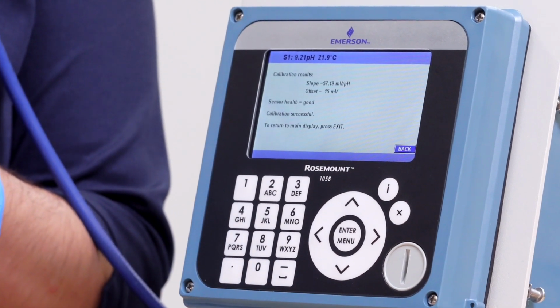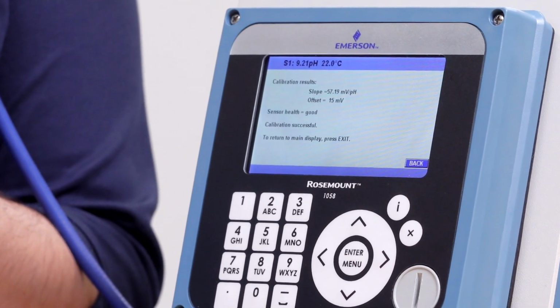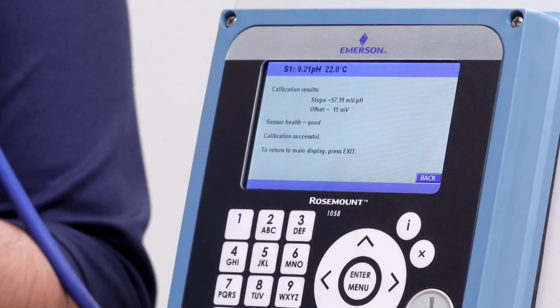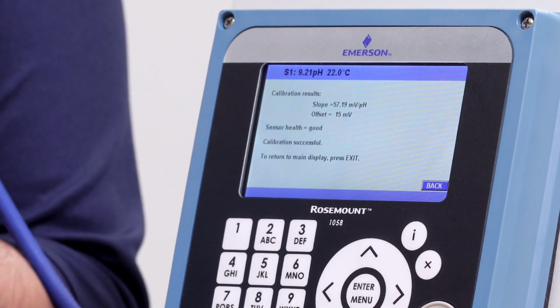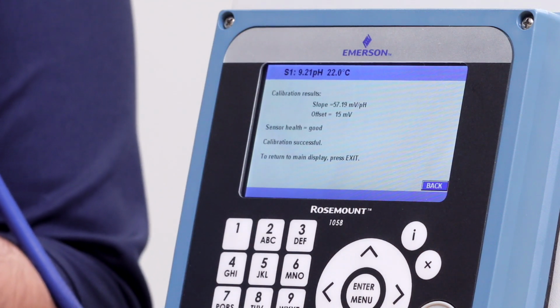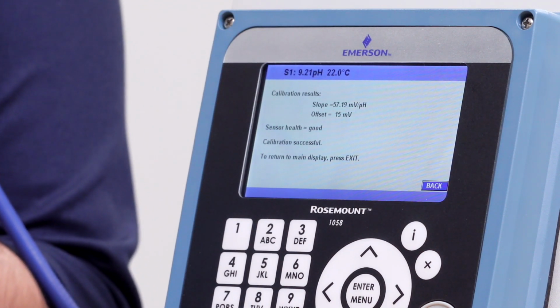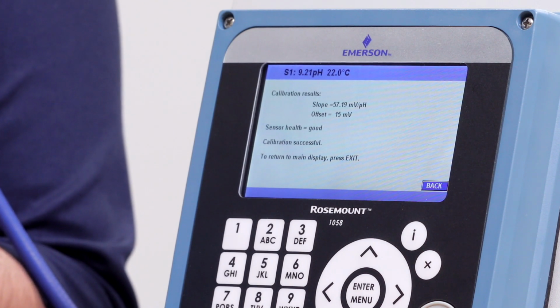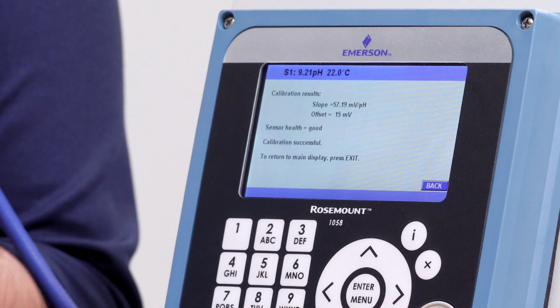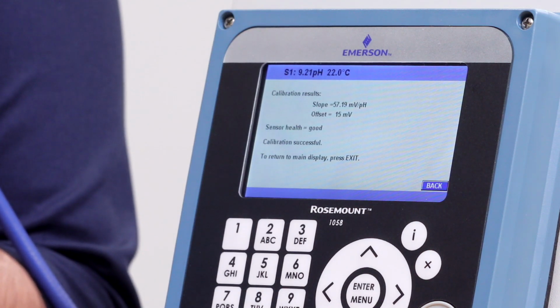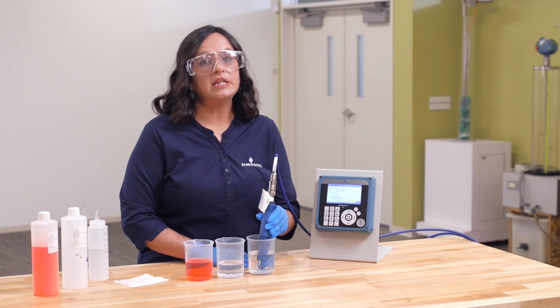Look at the slope to determine if the sensor needs to be replaced. An acceptable slope for a pH sensor is between 50 and 59.16. Ideally, a healthy pH sensor will have a slope between 57 and 59.16. The acceptable offset for a healthy pH sensor is between -60 and 60 millivolts. Ideally, a pH sensor will have an offset as close to 0 millivolts as possible.